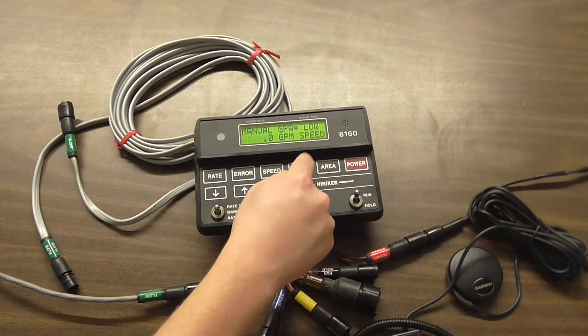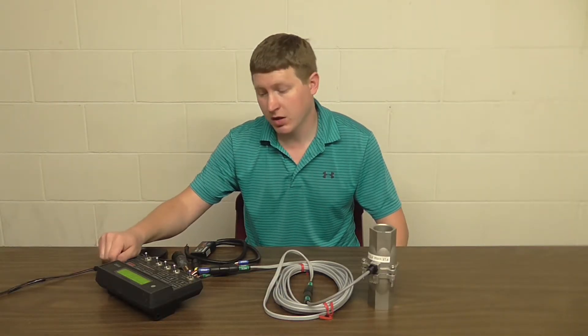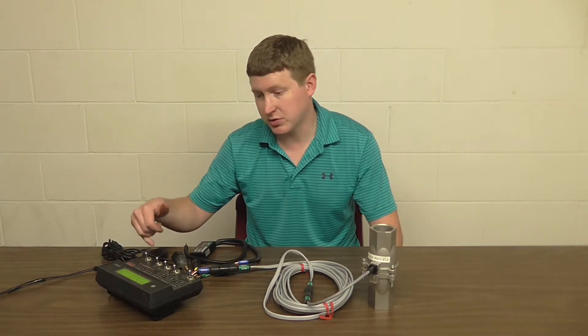Now to verify this, we can simply go and press the volume key twice, and get your volume per minute reading. And there you should definitely get a flow through the speed sensor.